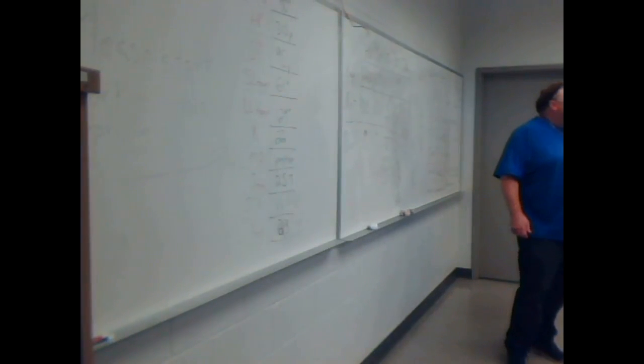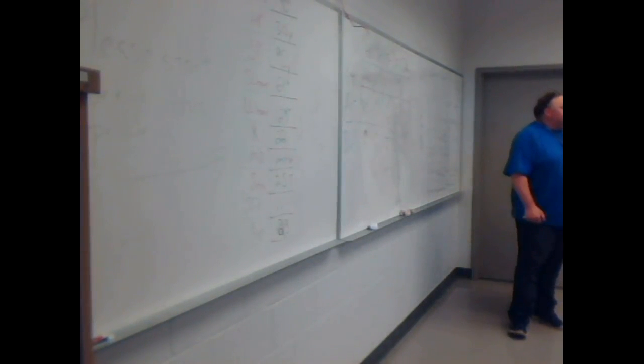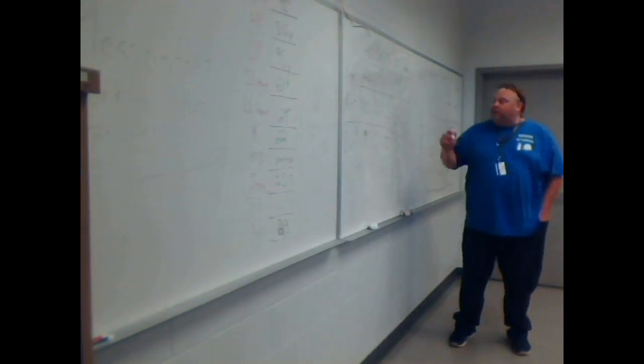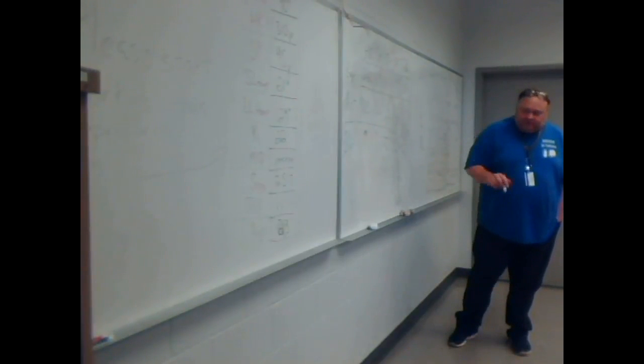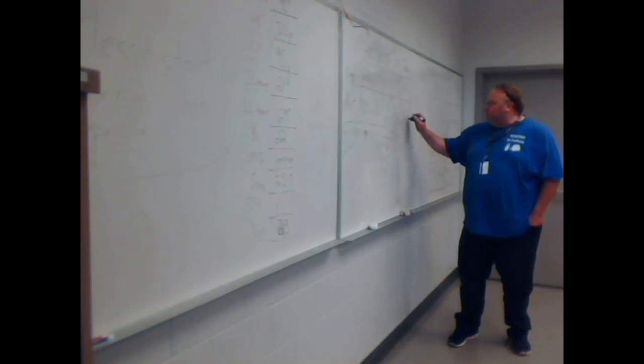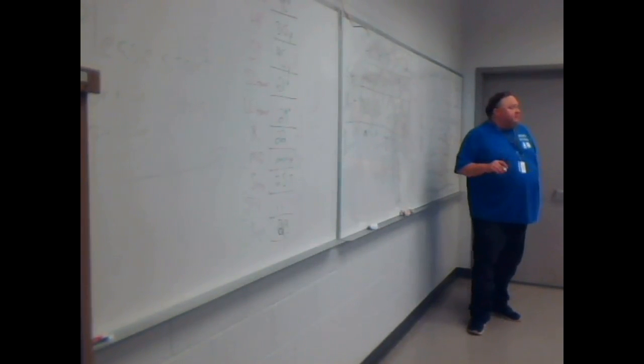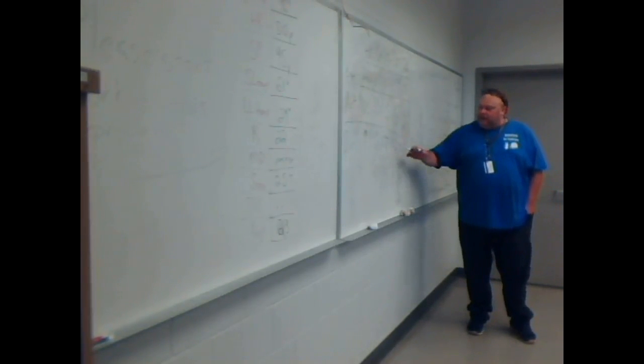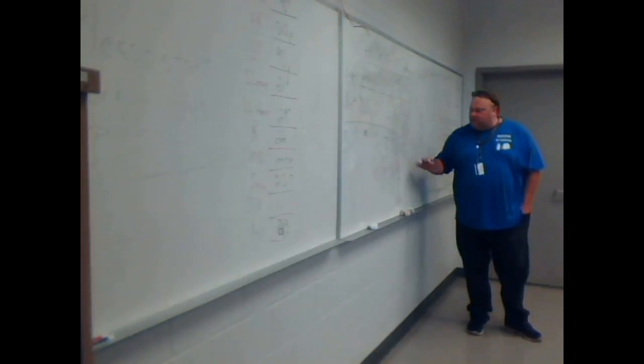My amp draw. This is a 2.5 ton unit. What would I expect my amp draw to be? 17.5, right? Because 7 per ton, unless it's on the data plate, which would be better. So 17.5. And we registered 23. Is this 23 above or below the expected? So I've got 2 up, then skip one down, and 1 up. Does that register with anything?